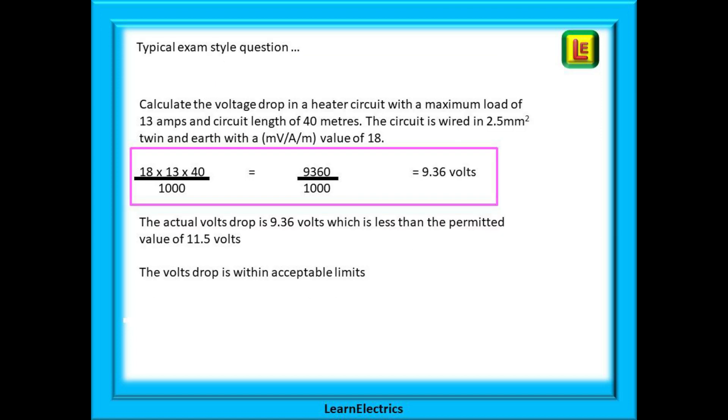Here is a typical exam style question. Calculate the voltage drop in a heater circuit with a maximum load of 13 amps and a circuit length of 40 meters. The circuit is wired in 2.5 millimeter twin and earth with a mV/A/m value of 18. All the information we need will be in the question. Again use simple steps to find the answer. If we do our calculation correctly we should have an answer of 9.36 volts. At full load this circuit will lose 9.36 volts into the cable.